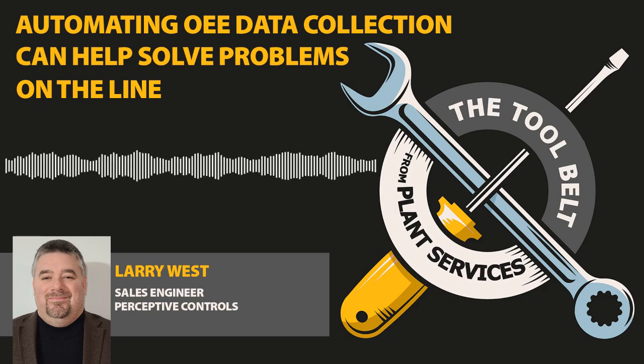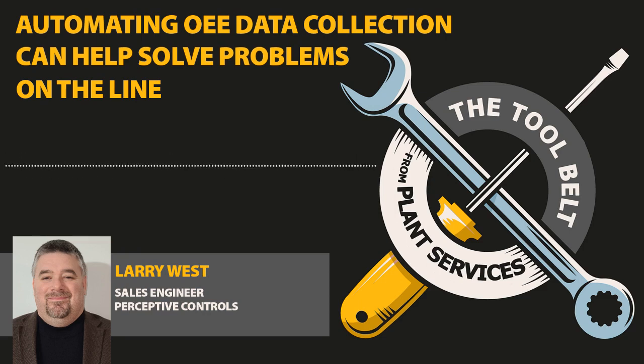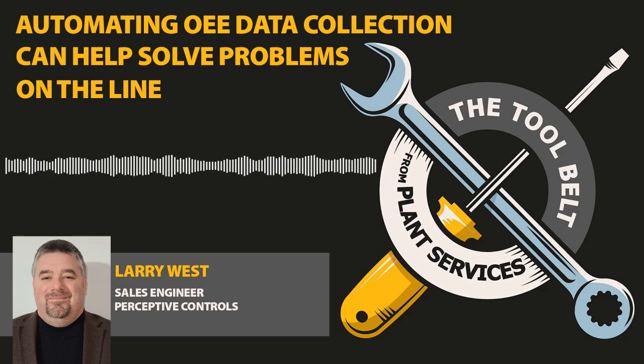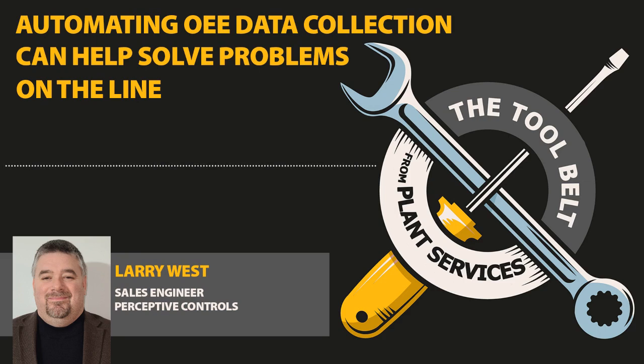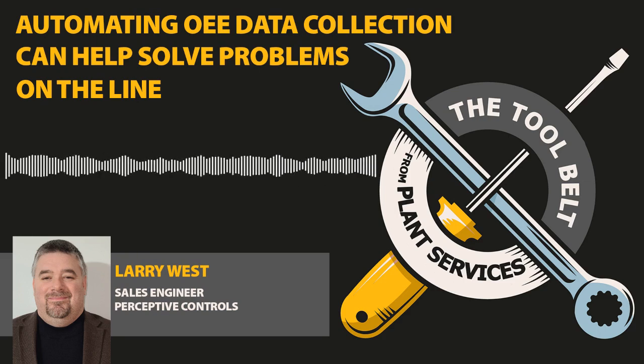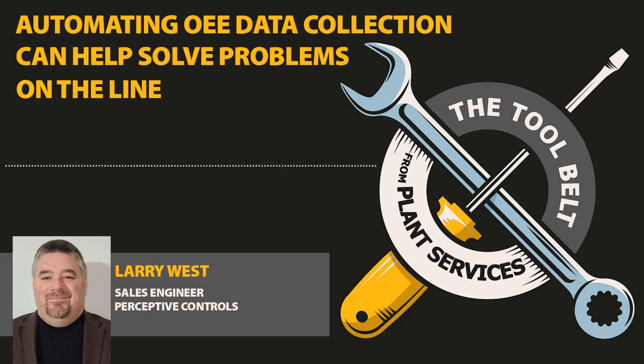From there, we know that the machine is running. We start recording runtime at that point. If the machine goes down for any reason, we automatically register that and say, okay, the machine went down. If there's information in the PLC that's readily available, it says the machine went down for X. Let's say a no rotation fault. We can automatically record that and say, okay, it was a no rotation fault. Once the machine goes back into operation, the machine goes into run. Nobody needs to do anything. It's a completely hands-off situation.